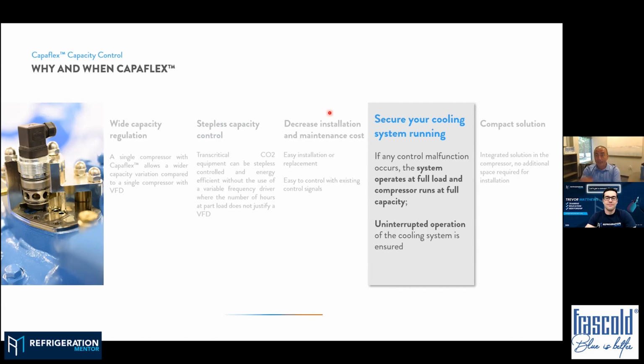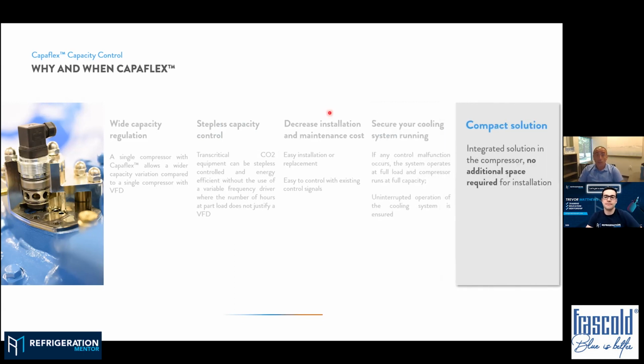In the design of this component we tried to eliminate - of course we weren't fully able to - but let's say 95% of possible failures will leave the valve in a position for the compressor to run at full load. So even if the system isn't working, in most cases the compressor will still run at full load. And yes, it's a compact solution.